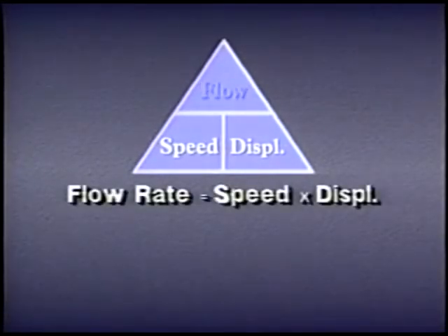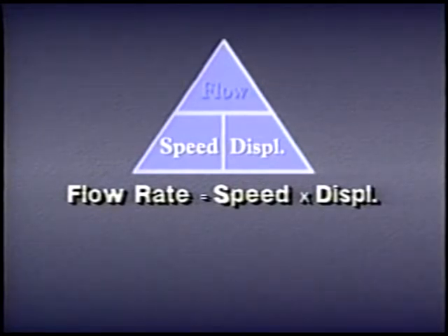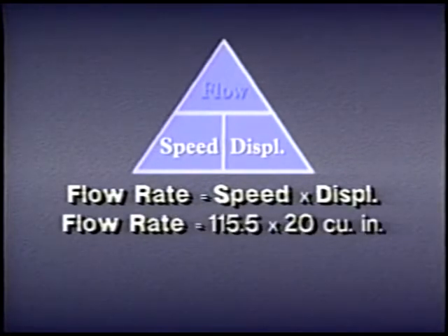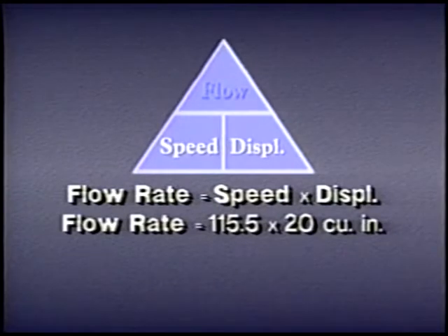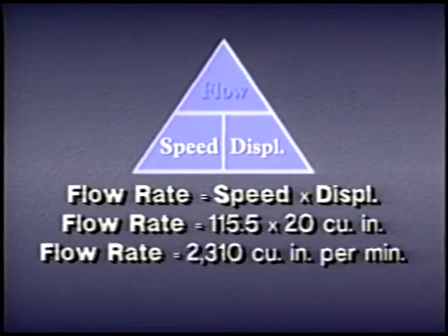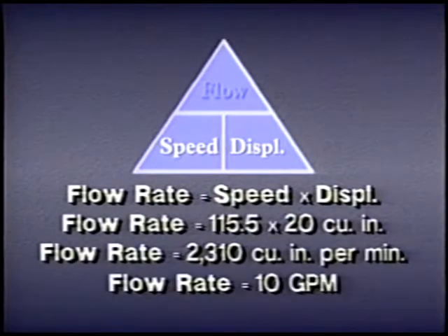We can also calculate the flow a motor requires to maintain a certain speed if we know the displacement. For example, a 20 cubic inch motor operating at 115.5 rpm will require a flow of 2,310 cubic inches per minute — that's 10 gallons per minute.